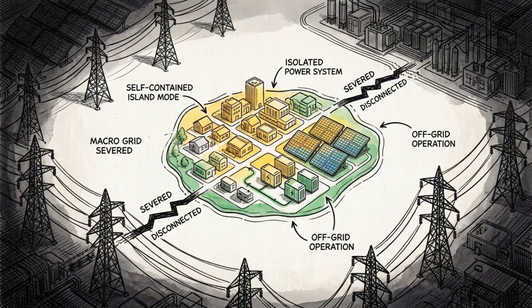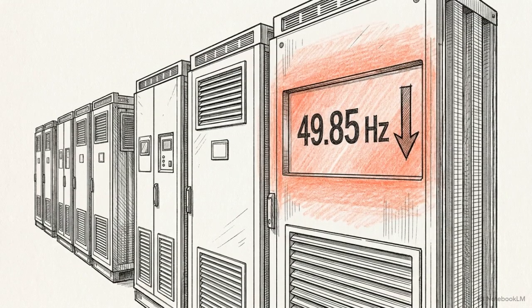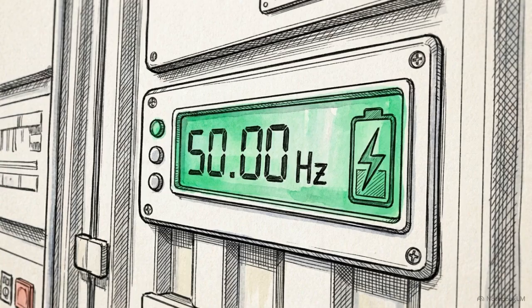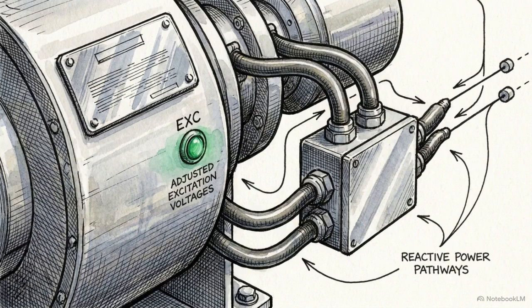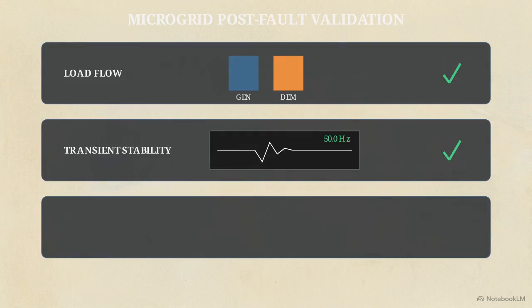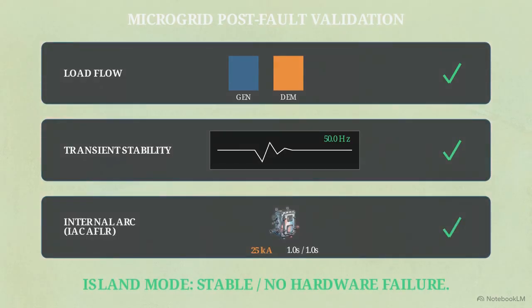from the surge. The electrical defense reacts just as fast. The battery storage system detects the sudden frequency shift caused by the physical isolation and injects stabilization power within milliseconds. Following the battery, the microturbines adjust their excitation voltages, taking over reactive power duties to stabilize the newly islanded network. Reviewing the post-fault metrics confirms the system logic held. We see verified checkmarks across load flow balance, transient stability, and arc fault containment. The islanding succeeded without hardware failure.